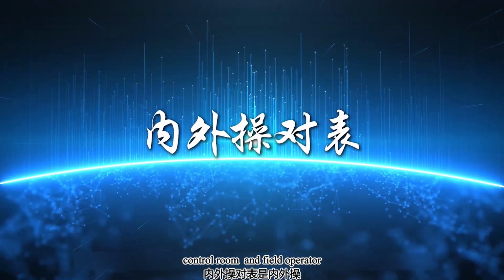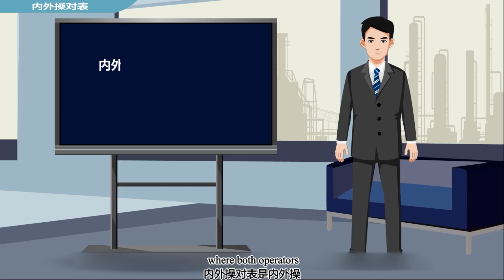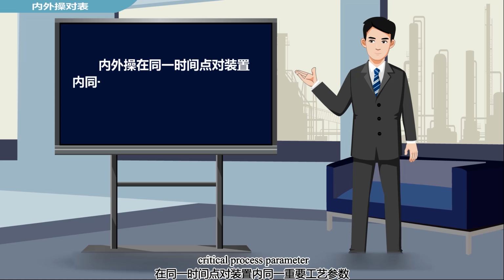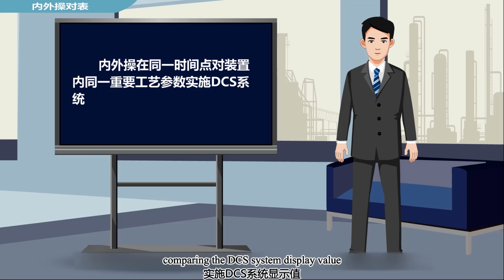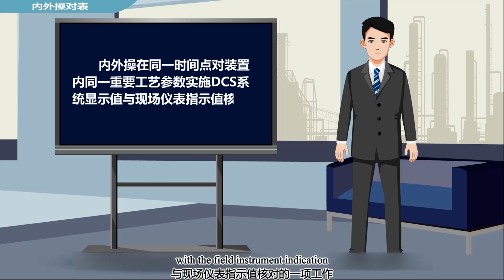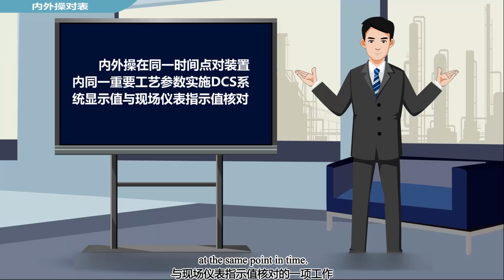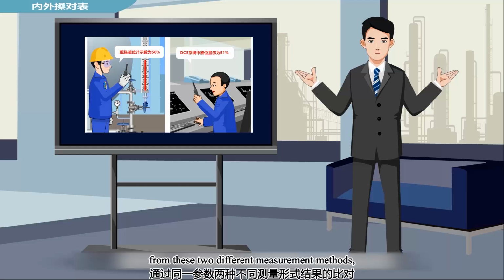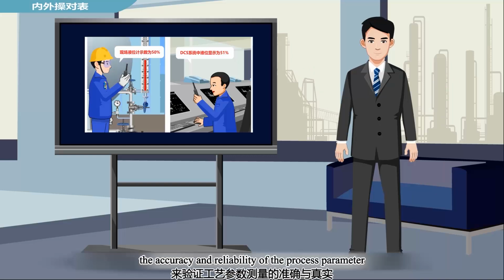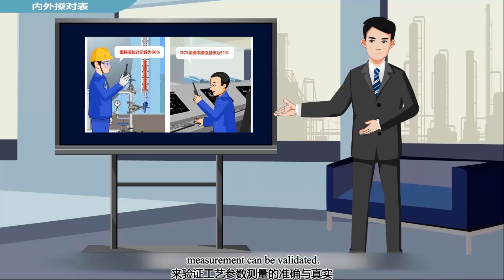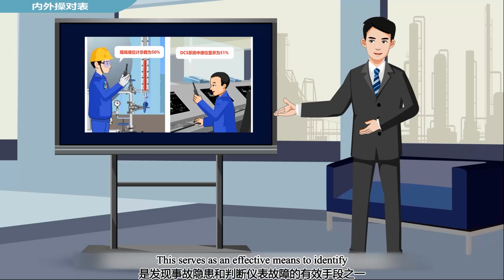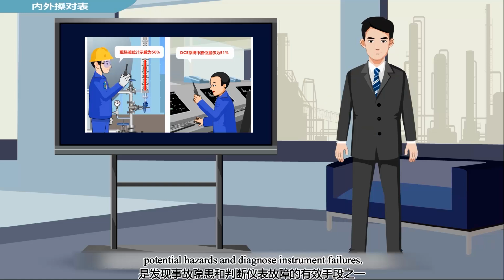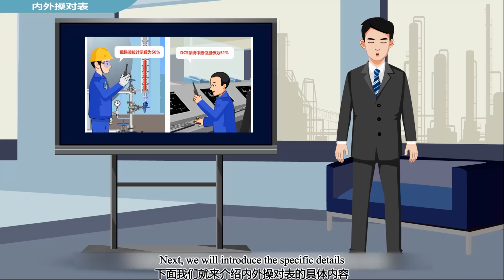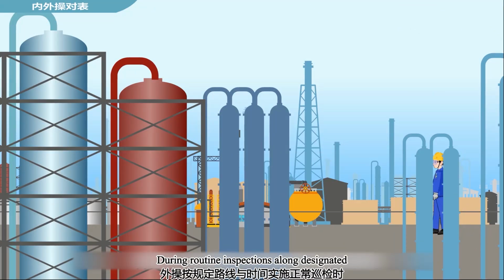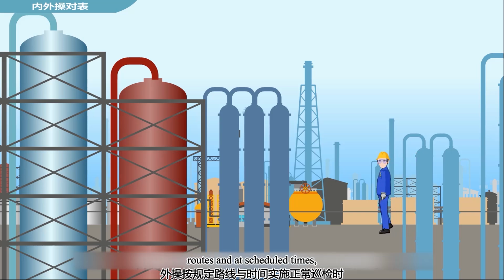Control room and field operator parameter verification is a task where both operators simultaneously check the same critical process parameter, comparing the DCS system display value with the field instrument indication at the same point in time. By comparing the results from these two different measurement methods, the accuracy and reliability of the process parameter measurement can be validated. This serves as an effective means to identify potential hazards and diagnose instrument failures. Next, we will introduce the specific details of control room and field operator parameter verification during routine inspections along designated routes and at scheduled times.